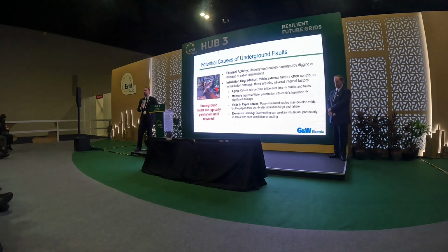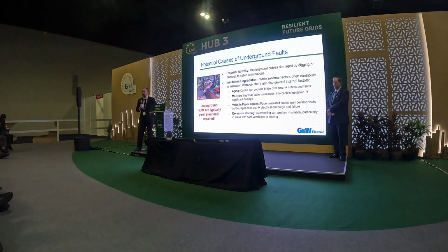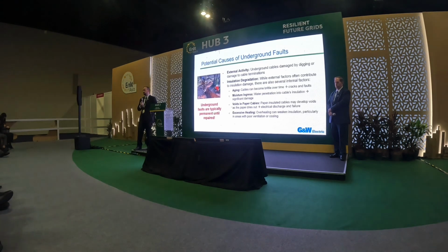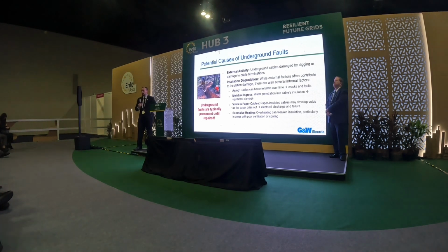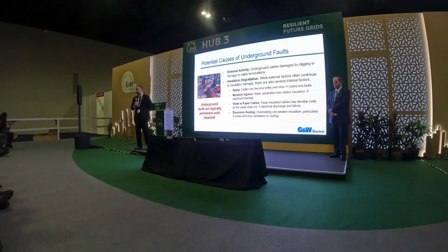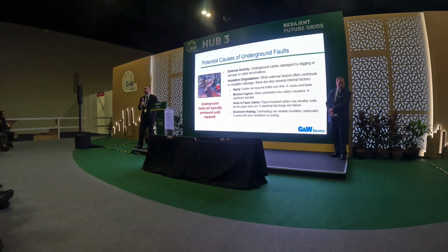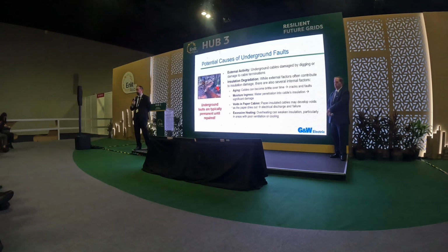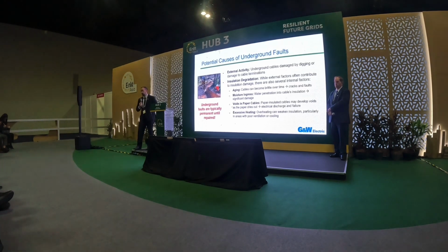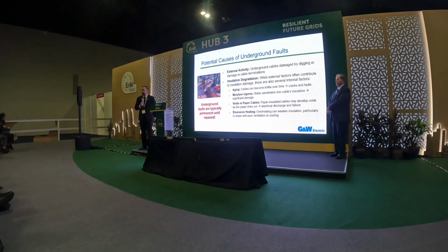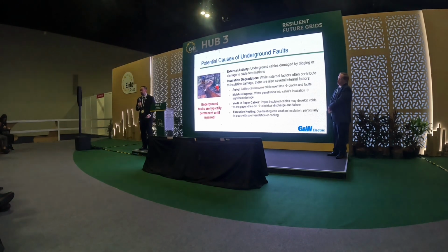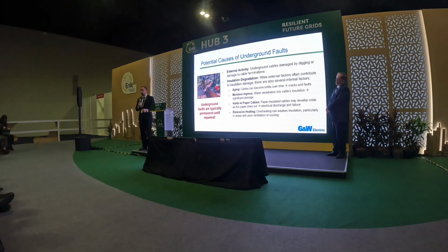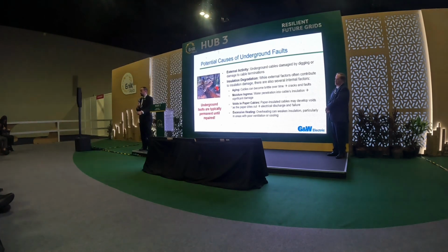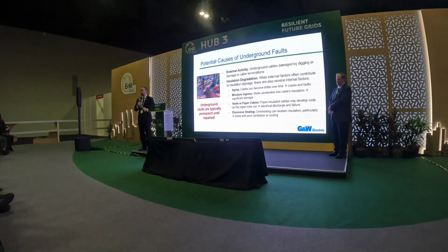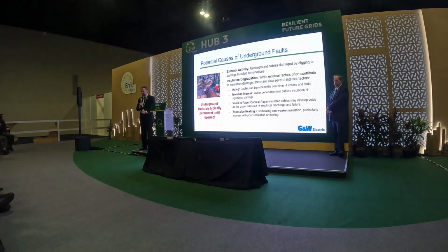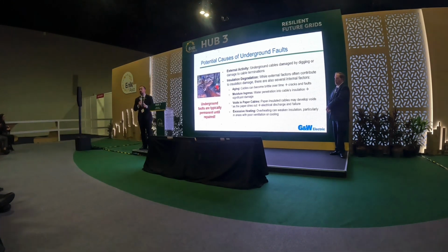And then last but not least, excessive heating. So if you're over-dutying your circuits with more current than they're rated for, and the impacts of faults, where there are short circuits and short amounts of high energy, that can degrade that cable insulation. One thing that's common in all of these is that typically when you have an event like this, it's a permanent event, meaning that short circuit is not going to heal itself without repairing that insulation. So we call that a permanent fault. Okay? It's a little bit different than what we see on overhead systems.